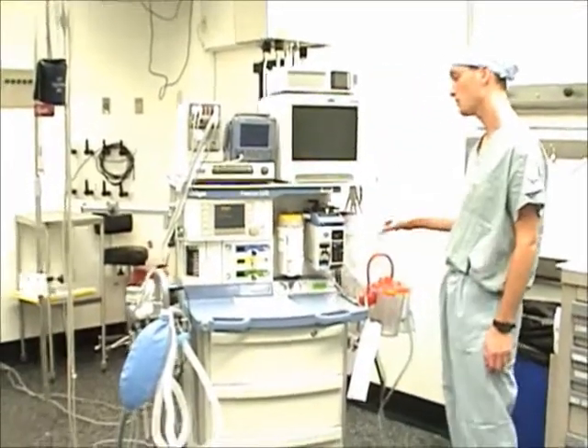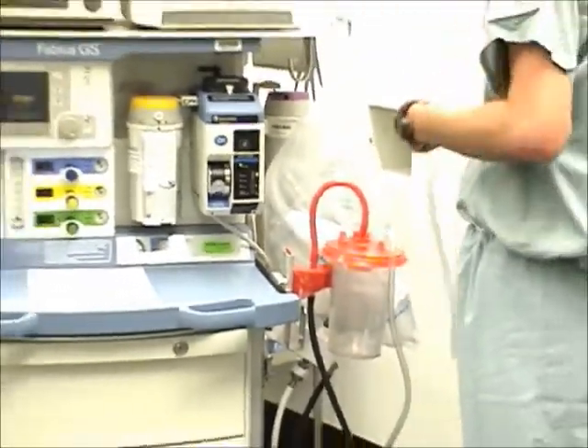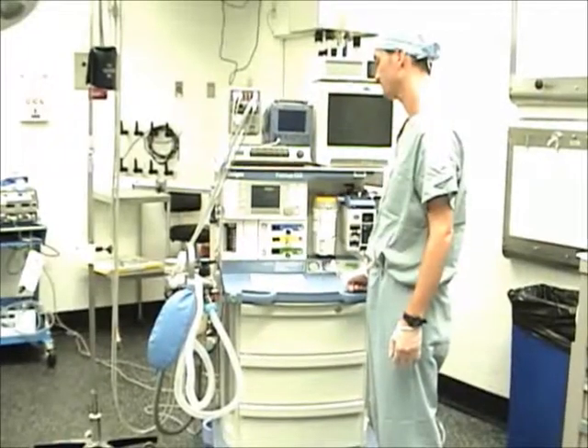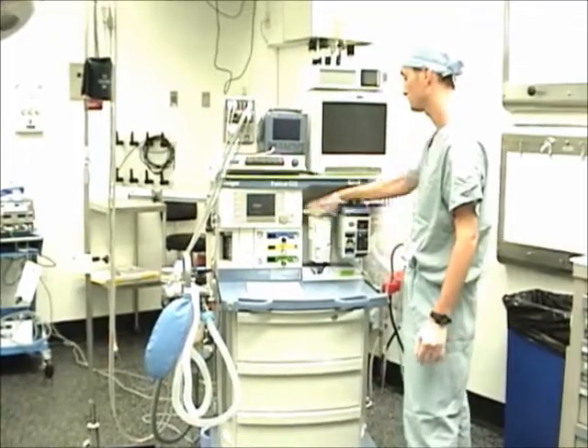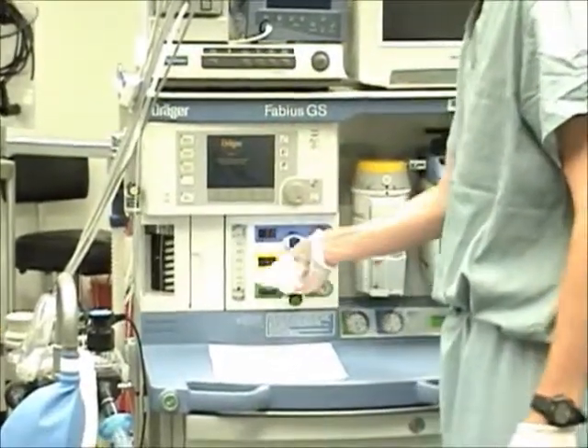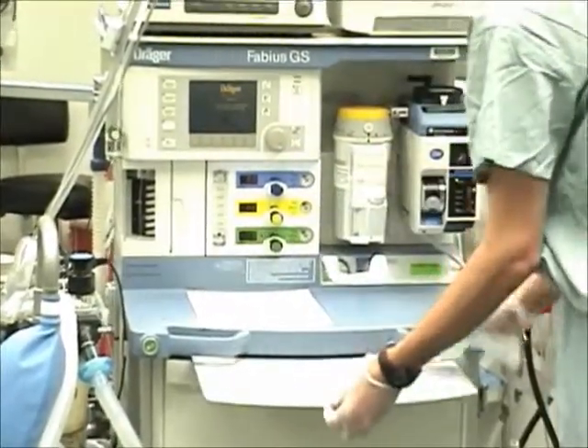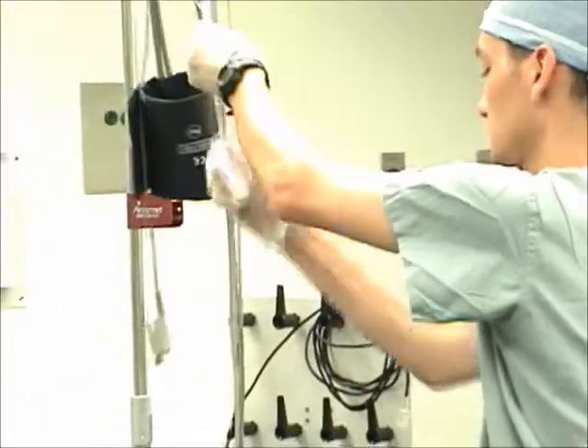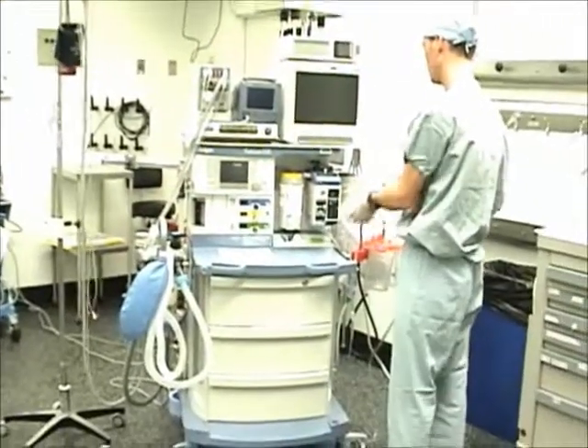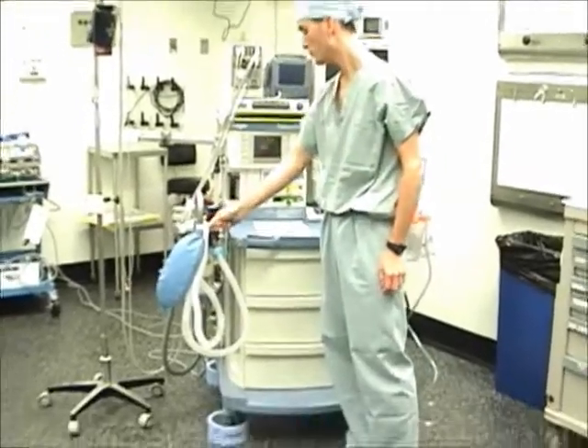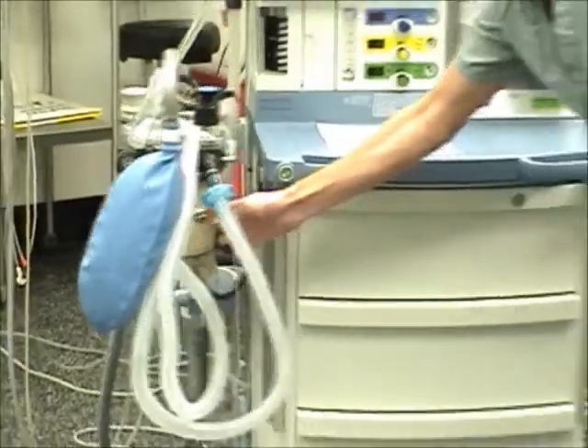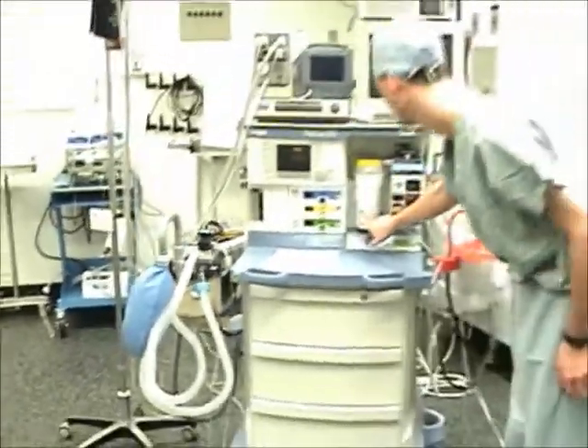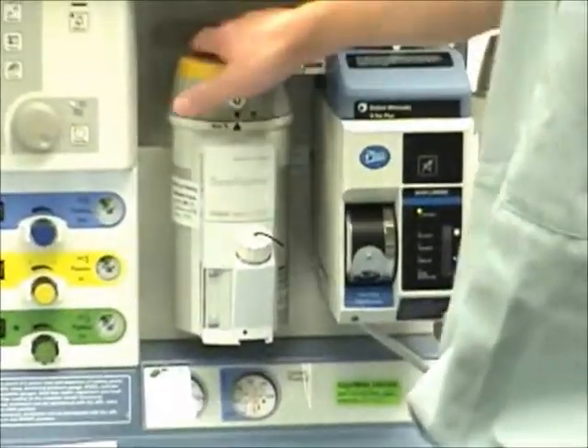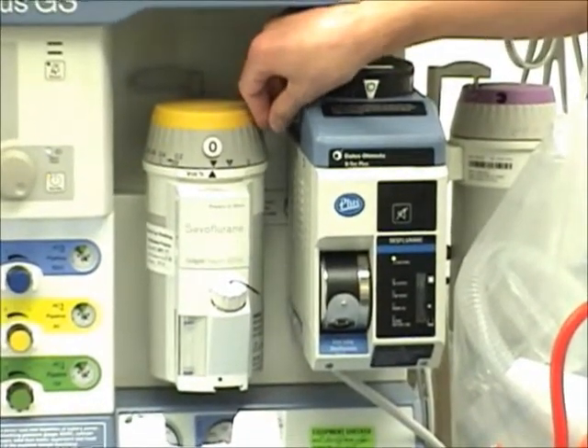First, verify the presence and proper function of emergency ventilation equipment and suction device. Next, wipe down all machine and monitor contact surfaces. If not already present, attach a patient breathing circuit to the machine. Verify that the CO2 absorbent is adequate. If present, the color change should be less than half the absorbent canister. Check that each vaporizer is full. Its dial is off, and that the interlock functions to allow the delivery of one agent at a time.